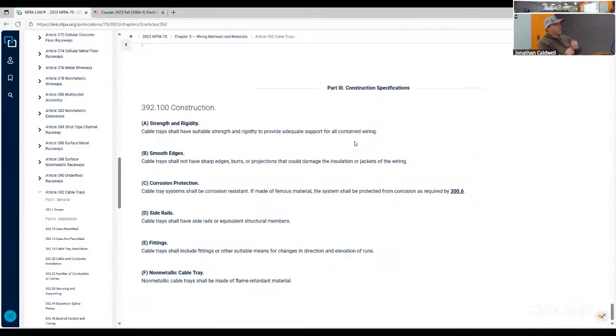I do want to say real quick, cable tray fittings is not what you think. Fittings can be part of the raceway. So fittings would go into like your nineties. They call them T's, they call them X's. They call them either Y's or vertical T's. There's a whole range of them. In fact, splice plates for these trays are not considered fittings, they're considered hardware in the manufacturer's eyes. So that's what I mean by fittings: it's essentially the raceway, but they are specific to whatever it's going. So 45s, 30s, all of the above. Typically out of supply, we make our own. We try not to buy the 45s and 30s because they never work out usually.